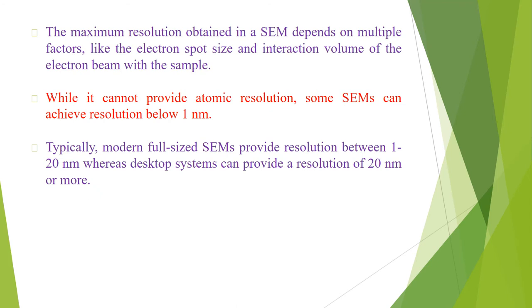The maximum resolution obtained in a scanning electron microscope depends on multiple factors, like the electron spot size and the interaction volume of the electron beam with the sample. While it cannot provide atomic resolution, some scanning electron microscopes can achieve resolution below 1 nanometer. Typically, modern full-sized scanning electron microscopes provide resolution between 1 to 20 nanometers, whereas desktop systems can provide a resolution of 20 nanometers or more.